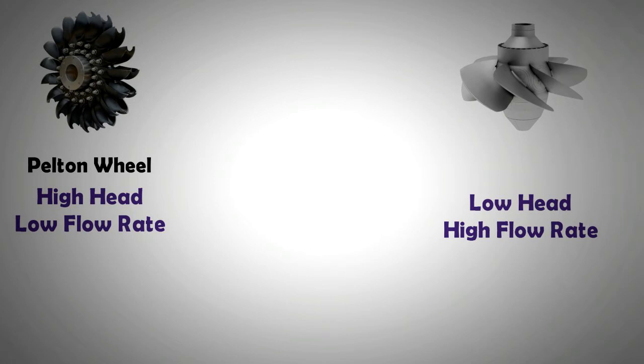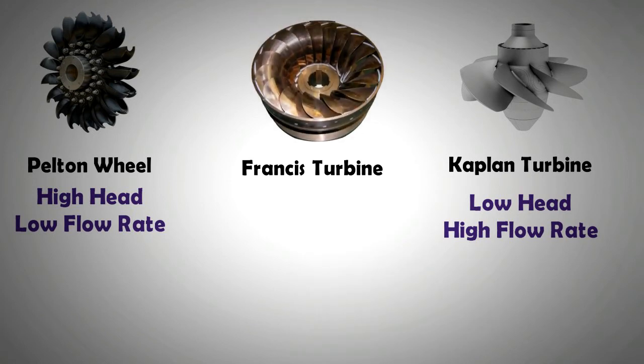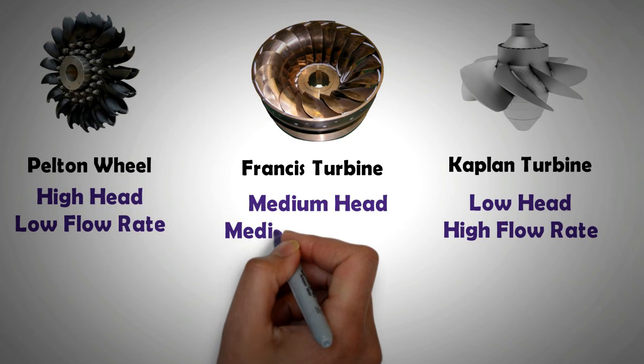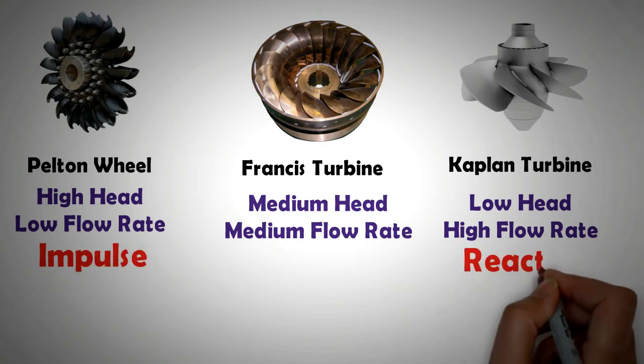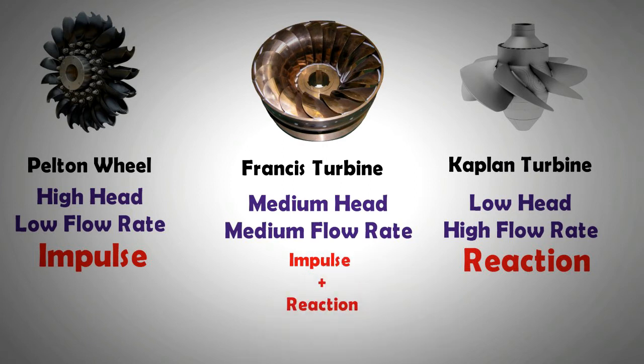Pelton wheel is an impulse turbine whereas Kaplan turbine is a reaction turbine. There is also Francis turbine which falls in the middle. Francis turbines are used for medium head levels and medium flow rates. The operational envelope of Francis turbine is very wide. It is a hybrid turbine in that it utilizes both impulse of the force and reaction of the force.